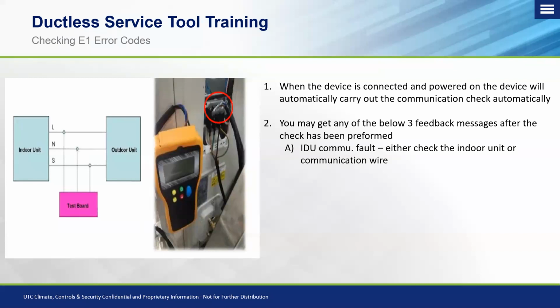Your first scenario is the tool comes up with an indoor communication fault. What that means is you either need to check the indoor unit or something within the indoor unit, or the wire going to the indoor unit. Oftentimes, especially in the summer, if you have a condensate pump that is broke through the signal wire and decides to fail, it will break communication. And if you're using the ductless service tool to troubleshoot that, this is most commonly the code that you're going to see on there, which would be an indoor communication fault.